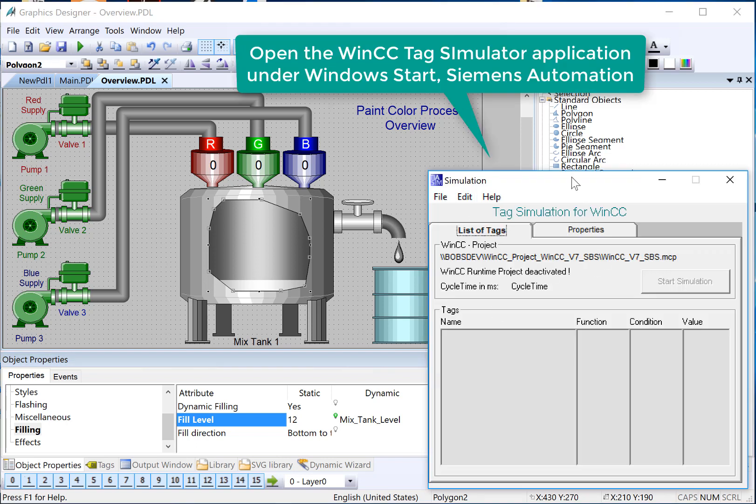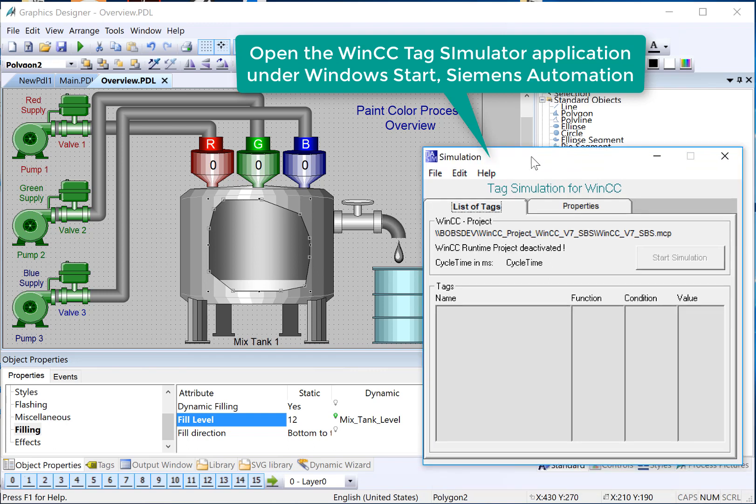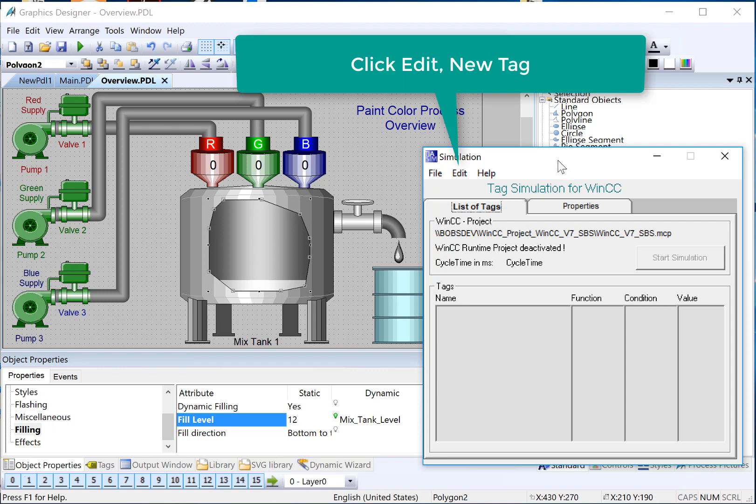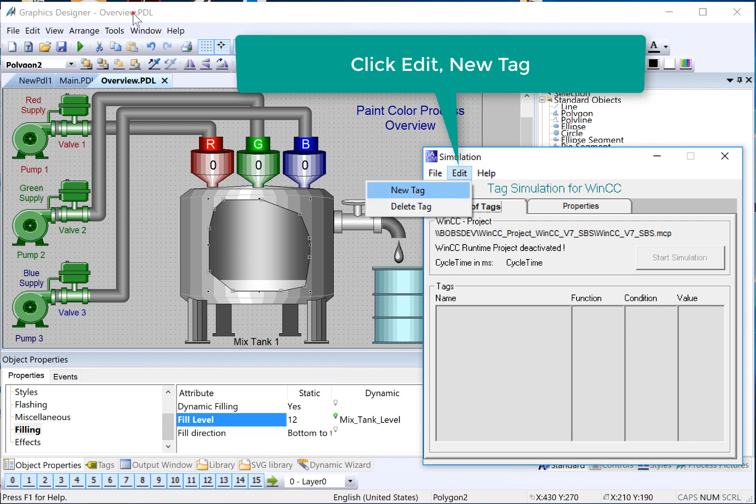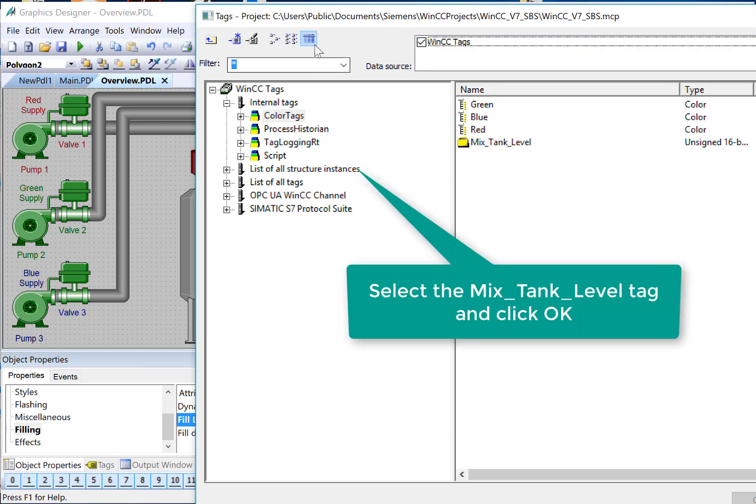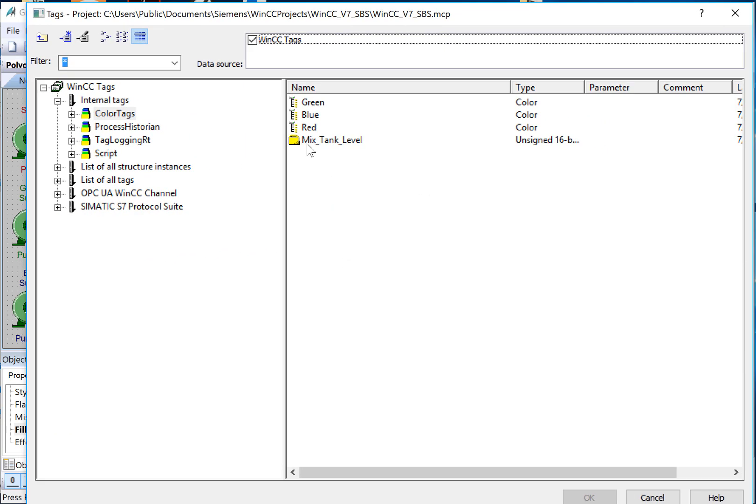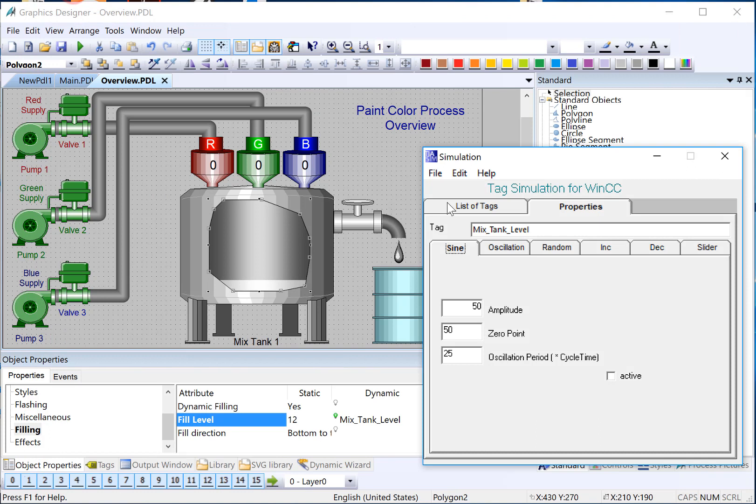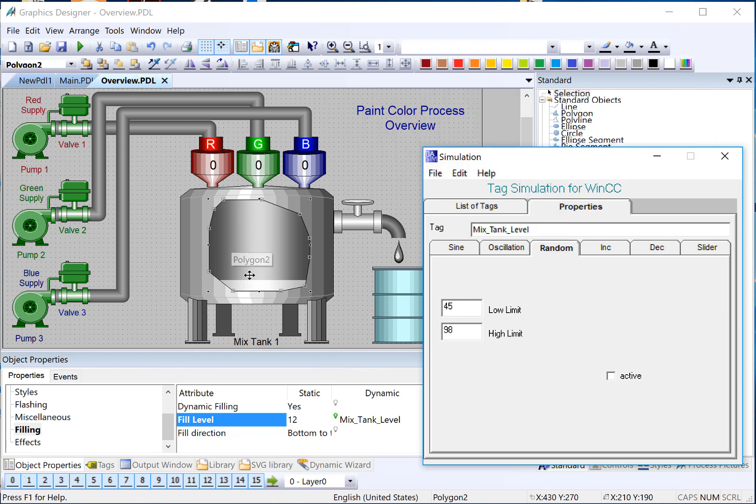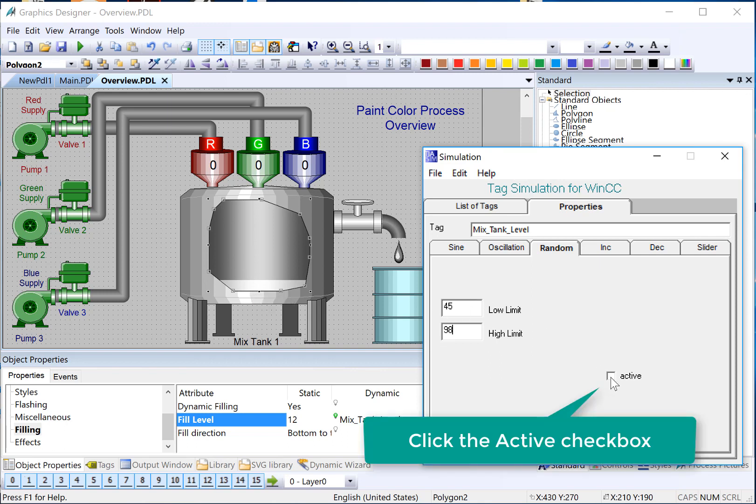The WinCC Tag Simulator ships with WinCC, and it can only be used with internal tags. So I've opened the WinCC Tag Simulator. It's usually found in the Siemens Automation folder on your Windows 10 or Windows 7 OS. So I'll choose Edit, New Tag, and it will give me a tag browser, and I'll just find the tag that I want to simulate. It will automatically open the Properties tab, and we just choose a way to simulate. So I'll just do Random between 45 and 98. The fill level only goes 0 to 100, so I don't really want to go above this. And then I'll just click Active.